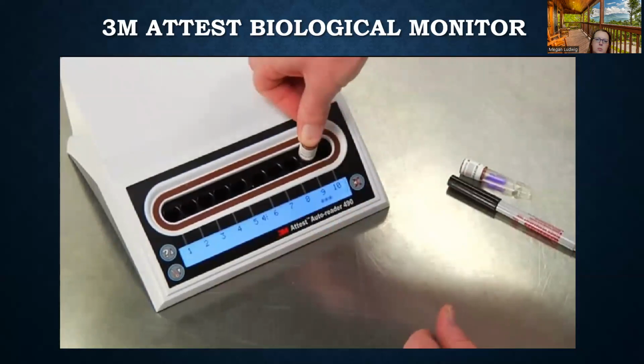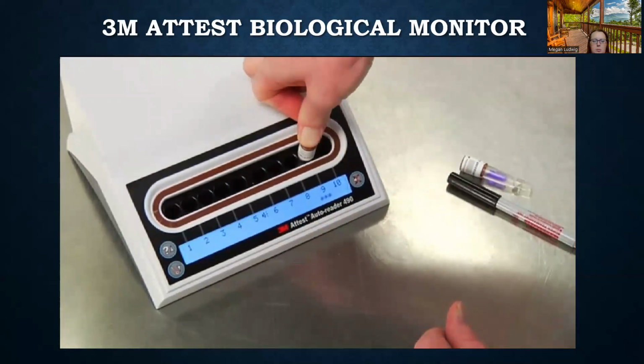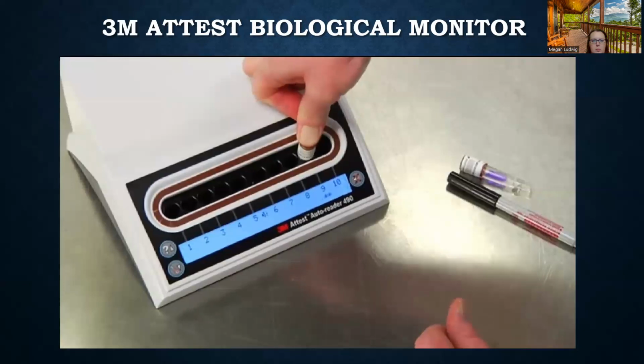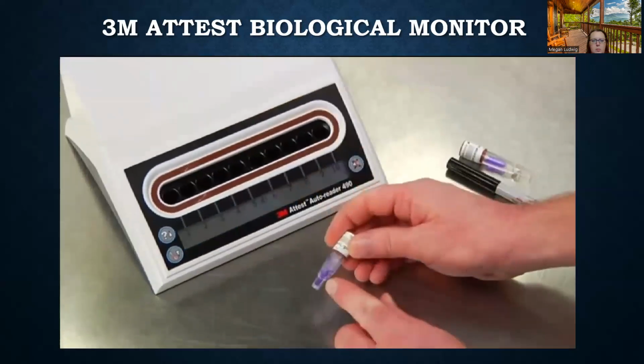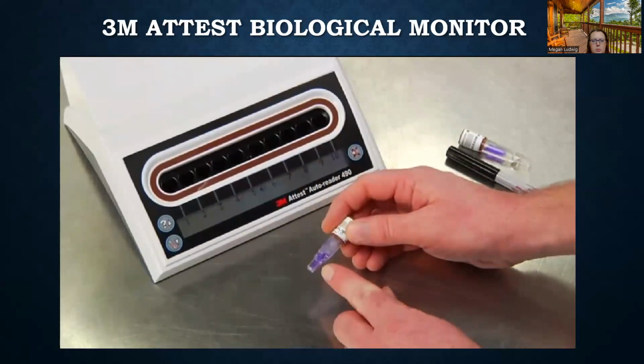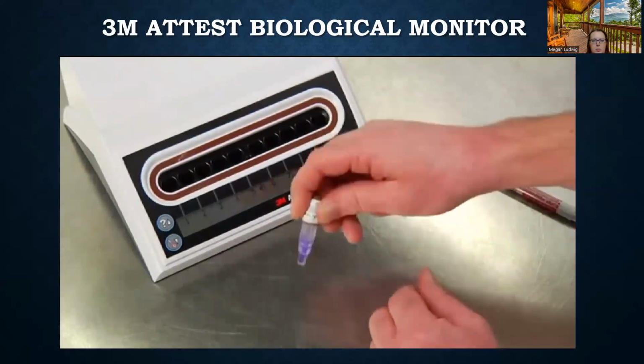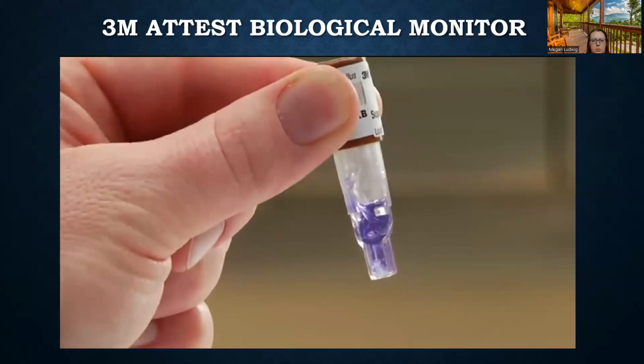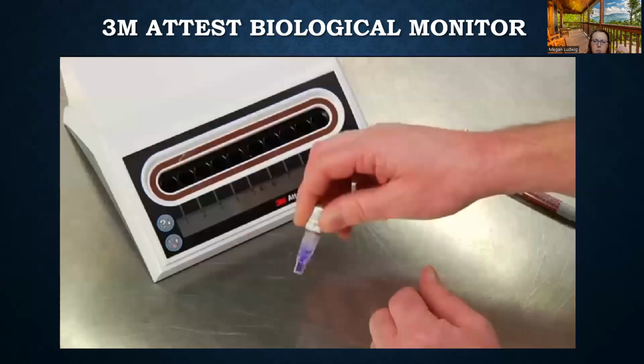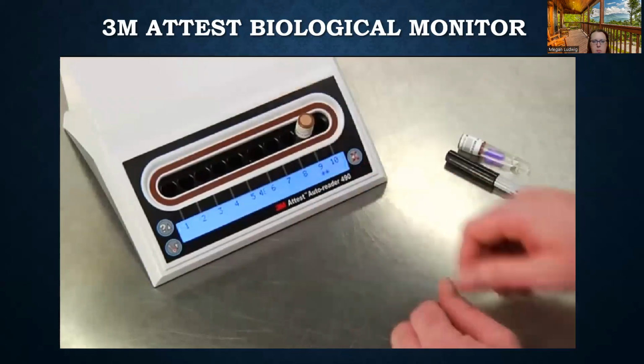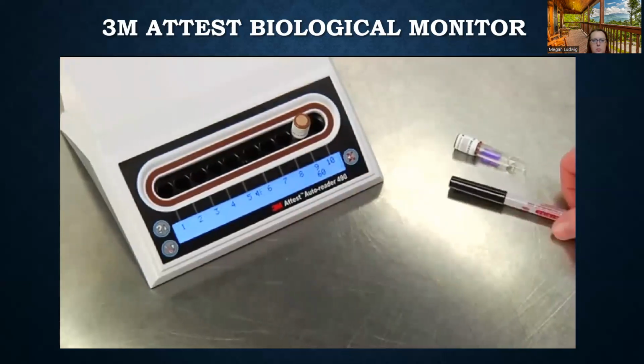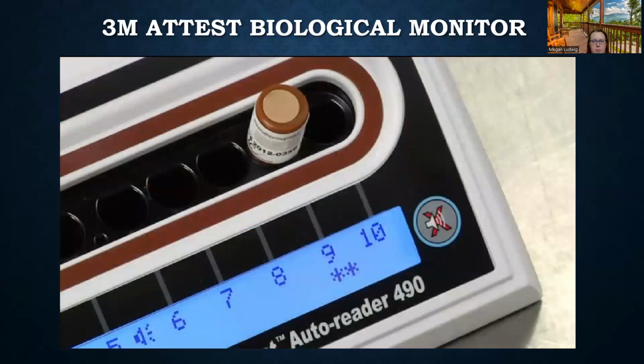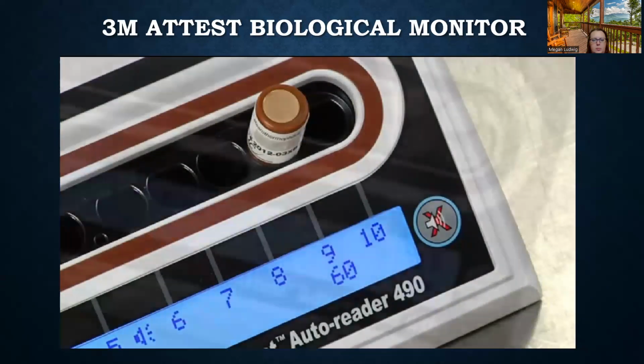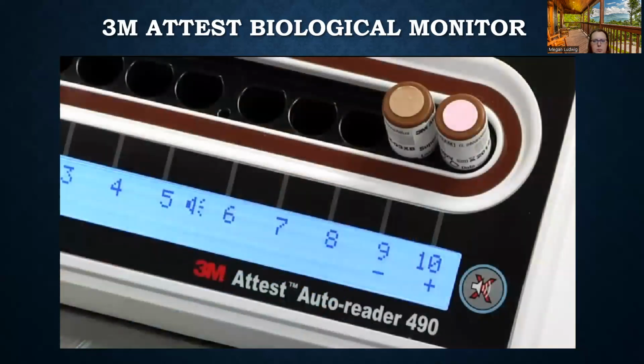Press the cap of the Attest Super Rapid BI down firmly to close the cap and crush the glass ampule. Immediately remove the BI and visually verify that the glass ampule has been crushed. Then, flick the vial to cause the purple growth media to flow to the growth chamber at the bottom of the vial. Return the activated BI to the incubation well and check the LCD panel to confirm that the vial is properly seated. The auto-reader LCD panel will display a series of asterisks, then the remaining incubation minutes right below the incubating BI. Now, all you need to do is wait for the result.